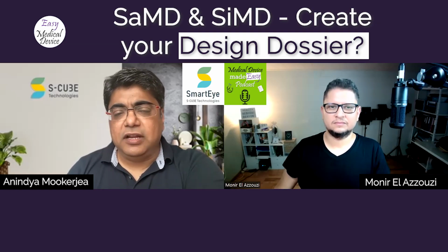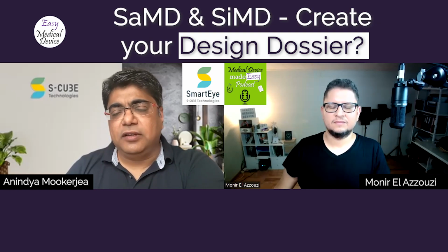And if your medical device is a software, or it is there to help the intended purpose of the hardware, then IEC 62304 is a recommended standard. It all starts from the 13485 platform, but then you need something specific to the software lifecycle. IEC 62304 is the most popular standard for the software lifecycle. So that's one of the recommendations.